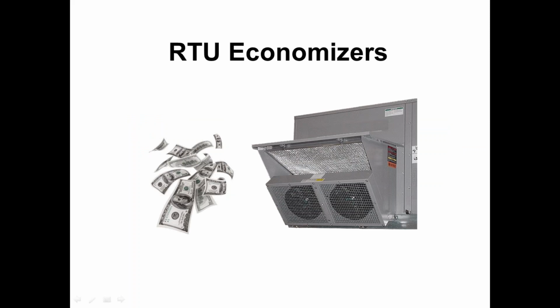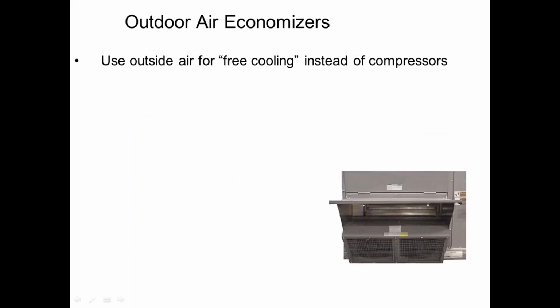All right, so economizer. We're going to spend some time talking about this because this is a pretty active part of what a rooftop is, and there is some good energy savings from it. Most of you guys know what an economizer is. It's essentially our way of opening a window in a commercial building where windows either can't be opened or they're not easily opened or they're opened by occupants that don't know what's going on, right? So instead, we open a window inside the mechanical unit and bring in the cool, free air that way.